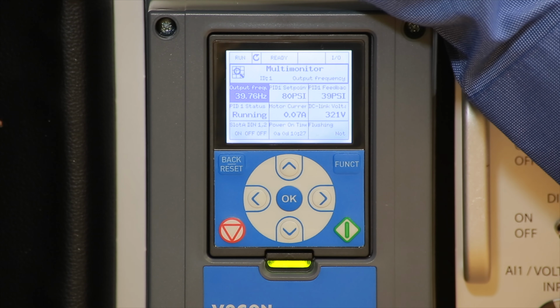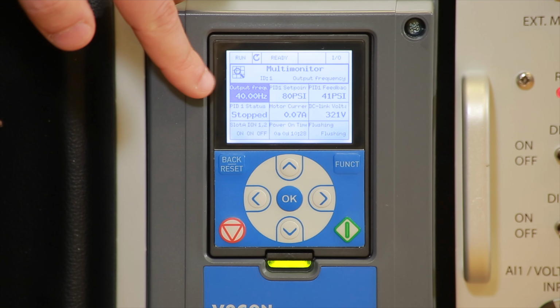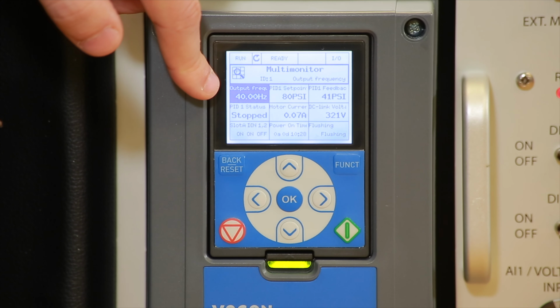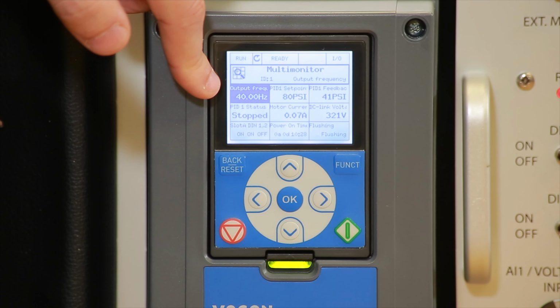And this is activating the flushing sequence of the drive, which runs at 40 Hertz until we want to stop it. So it doesn't matter what the drive is doing. When we activate the flushing sequence with another digital input, it overrides whatever we're doing. So it's really, really good that way. So you can see both of the digital inputs are on. So it's really, really good.